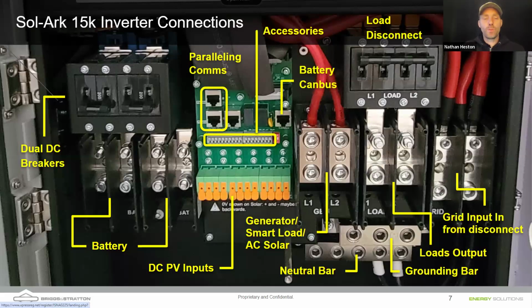If you're paralleling multiple inverters, I'm not going to get into how to parallel inverters in this talk in terms of programming. It's a relatively straightforward thing to do, but you would use those paralleling comms there. You only need one cable, and you go from inverter 1 to inverter 2 so that those inverters can share information. The battery CAN bus port there, those are all RJ45 or Ethernet type plugs. The battery CAN bus you will utilize if you're using those Briggs and Stratton stackable communicating batteries or other brands of batteries.